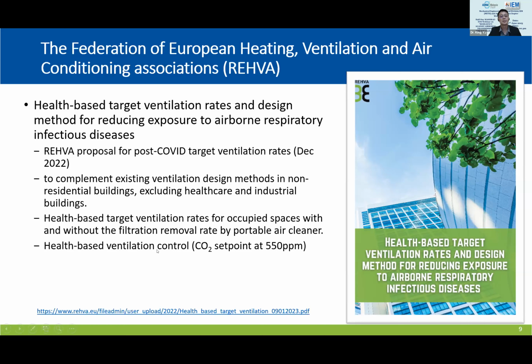The other one is on ventilation control, because at the moment some systems are using CO2 as a set point to turn on the ventilation. So the suggestion here is we can lower the set point to 550 ppm instead of a higher ppm, so that the ventilation kicks in earlier when there are only a few people in the space.